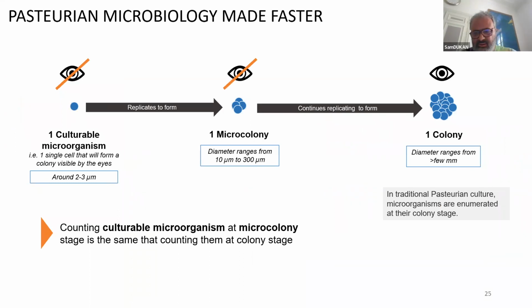Normally, the standard method detects the object at the stage of a colony that is visible by the eyes. Using our solution that combines 3 different approaches that potentially label specifically Legionella pneumophila, and some optics and mechatronics that are able to take pictures of the membrane, and some machine learning process, we are able to detect specifically the microcolony of Legionella pneumophila, which makes it possible to deliver results in colony forming units, but faster compared to the standard method.